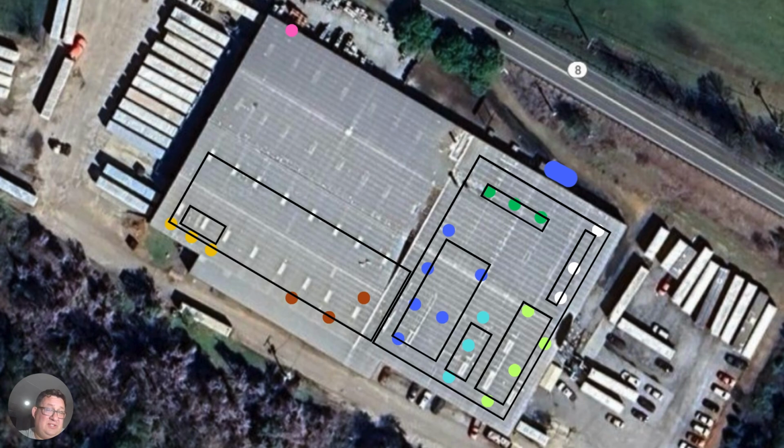One of the cool things that you can do is you can also determine by putting a flow meter and pressure transducer at the individual subloops. Now you can actually measure how that process group is utilizing compressed air, and you can hold that process group accountable all by itself, independently from the rest of the facility.